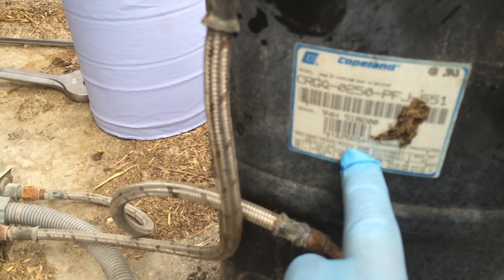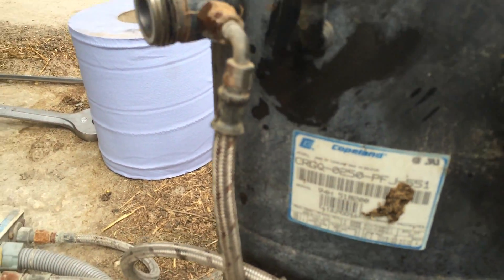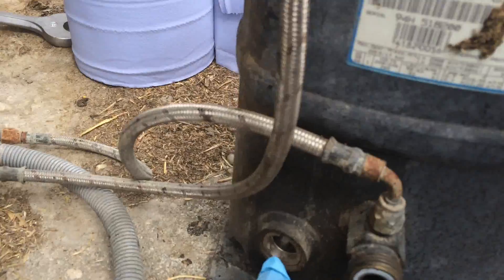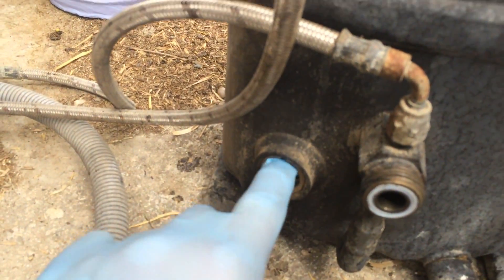These hold about 1.5 kilograms. Sometimes the charge amount stays on the data plate. It'll just fill it out so there's a nice level in the sight glass — just about half to three quarters full. There's lots of fresh gas as well.